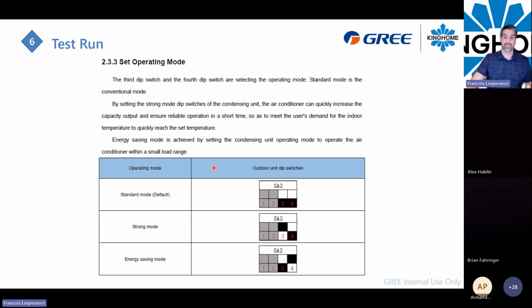Number 3 and 4 are the operation mode. We talked earlier about a half-ton unit. Well, there's no half-ton unit, but you can use this operating mode to use the system in a strong mode. For example, if you have a 3-ton and everything is connected for a 3-ton unit, you will use it in standard mode. If you need to bring more capacity to that unit, to make it act like a 3-ton and a half, you can use the strong mode. That will accelerate the algorithm, the compressor speed and everything, to act more quickly. So it will act like a 3-ton and a half.